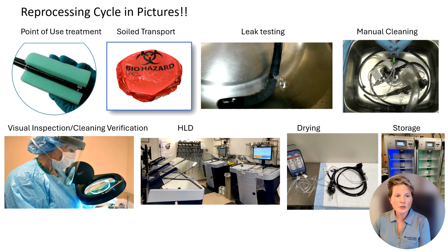Then once you take it out of the sink, you are to be visually inspecting it, and not just with your naked eye, ideally. Hopefully you're using some really good magnification and some extra good lighting as well. And then in addition to doing the visual inspection, for the high-risk scopes, it's really important to do cleaning verification, some sort of method of cleaning verification. One of the tests is that you can just look at the color change. You can test for protein, you can test for hemoglobin or carbohydrates, or you can test using an ATP meter of some sort. After that has passed the test, hopefully, you're going to move on into the HLD or sterilization part.